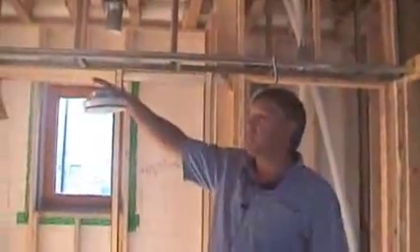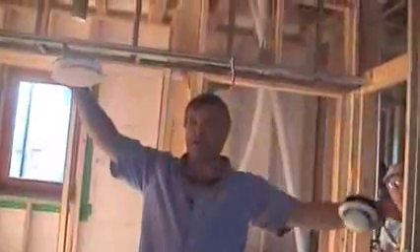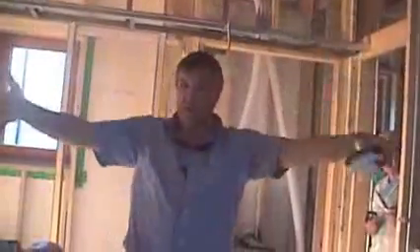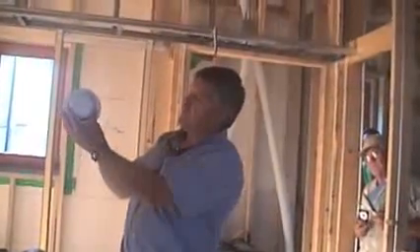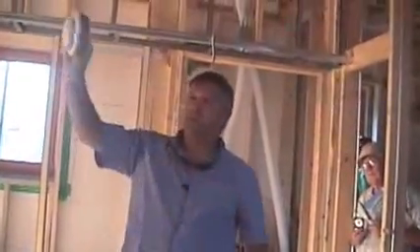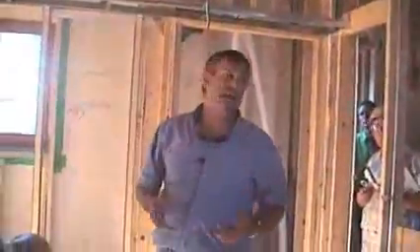So this would be on the supply points, the return points. The kitchen and bathroom would use this other return diffuser. And we can adjust the flows in those just by screwing that in and out. The supply comes out 360 degrees along the ceiling and does this. The return diffuser is a cone, and that can also be adjusted with the height of that, and that's the return diffuser.